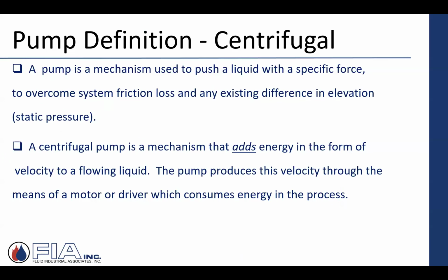Real quickly, a definition, centrifugal. So real quickly, a pump itself. A pump is a mechanism used to push a liquid with a specific force to overcome system friction loss and potentially, if it's an open system, any existing difference in elevation. When you talk specifically about a centrifugal pump, it's a mechanism that adds energy in the form of velocity to the flowing liquid. And then the pump produces that velocity through a driver, or in this case, a motor, which obviously consumes energy in the process.